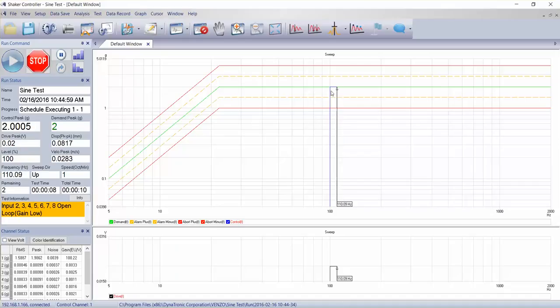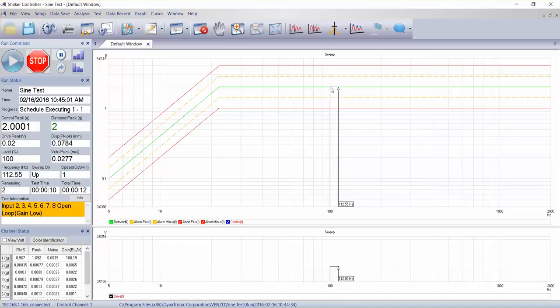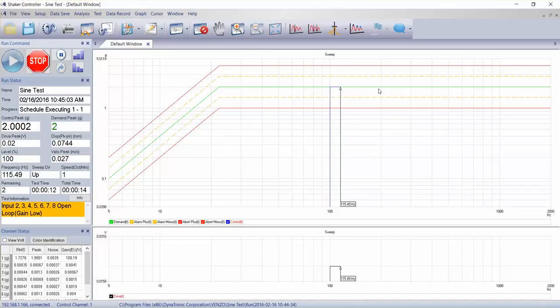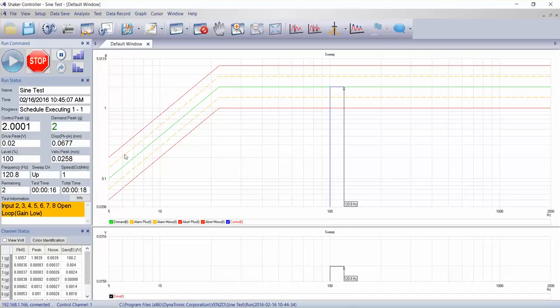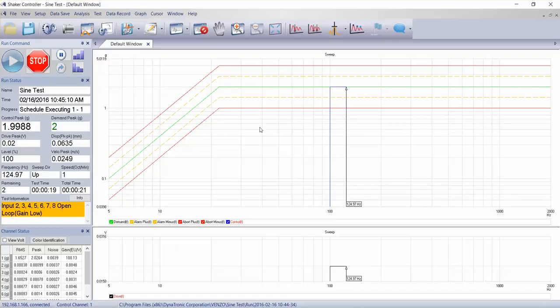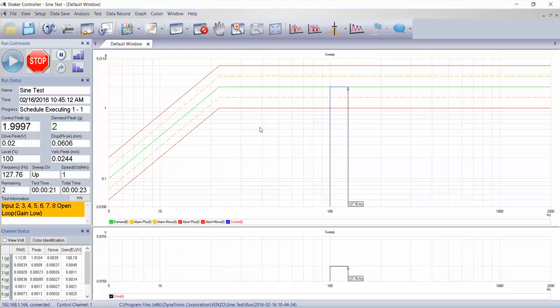Even though the low frequency of my breakpoint table is 5 hertz, so in this instance, in my schedule, I say sweep up from 100 hertz. So it'll sweep up to 2000, now sweep down to 5 hertz, and it'll continue the sweeps back and forth for as long as I have defined my test.